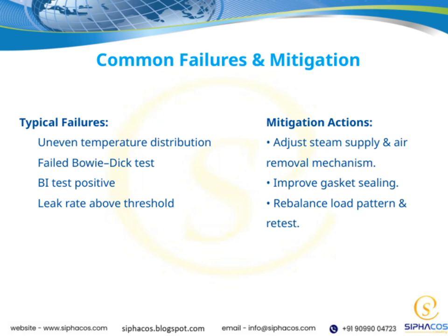When we talk about common failures, it's important to recognize these typical issues. Uneven temperature distribution can compromise sterilization, so identifying and fixing it is essential. A failed Bowie-Dick test is a red flag indicating that the sterilizer isn't effectively removing air, which can hinder sterilization. A positive biological indicator test suggests contamination, and a leak rate above threshold indicates potential breaches in the sterilizer's integrity. Addressing these failures with the right mitigation actions is critical to maintaining the safety and effectiveness of our sterilization processes. This connects directly to our overall goal of ensuring reliable sterilization outcomes and patient safety.